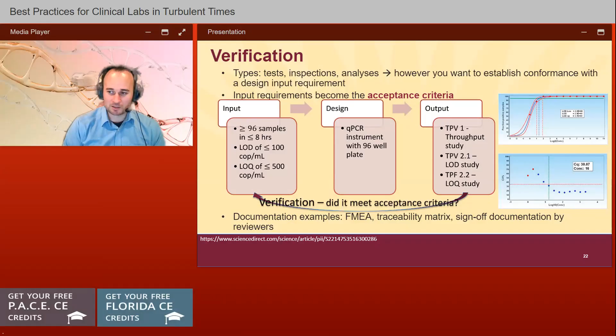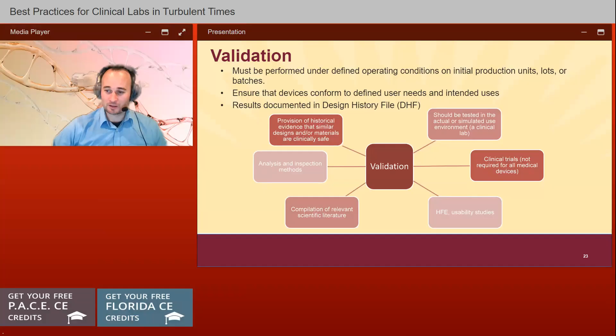Validation is the next stage where verification is asking the question, does the device perform well? And does it meet the specifications that we set? Validation, on the other hand, is asking, does my device meet user needs and the intended use of the lab test? And so ways to validate that we met user needs, the most simple example, though a lot of time and money, is clinical trials, validating that your test meets the user needs and has the appropriate sensitivities and specificities for patient samples. You can provide historical evidence that similar designs and materials are clinically safe, analysis and inspection methods, compile relevant scientific literature. As I mentioned before, human factors engineering or usability studies, validating that we're meeting the user needs of the lab staff, making it easy to use, easy to operate, things like that.